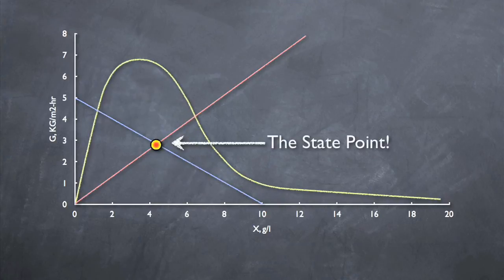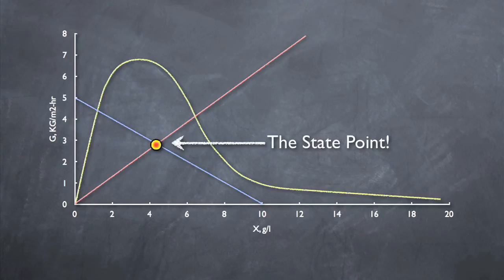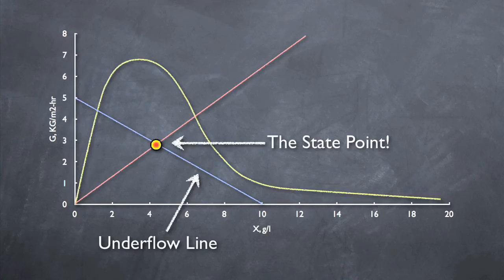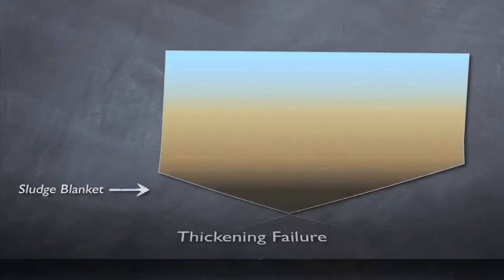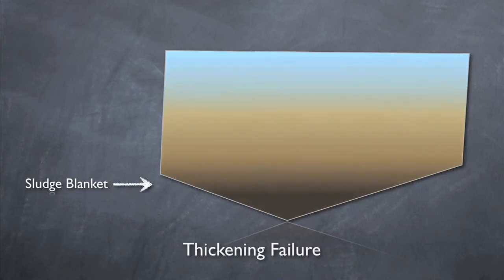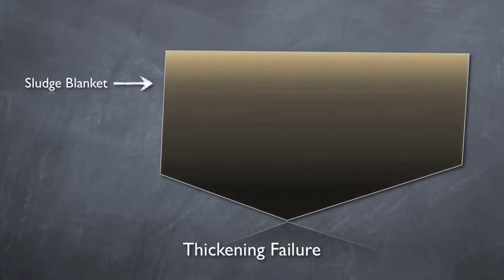However, getting the state point under the curve isn't the only goal. In order to ensure proper thickening of the sludge, we want to make sure that the entire underflow rate line to the right of the state point falls under the settling curve as well. If the state point is under the curve, but the entire underflow rate line isn't, the clarifier is failing in thickening. This means that sludge is settling in the clarifier, but isn't being removed fast enough. Under these conditions, the sludge blanket would rise in the clarifier until solids are passing over the weir.